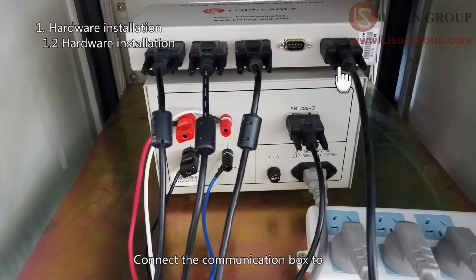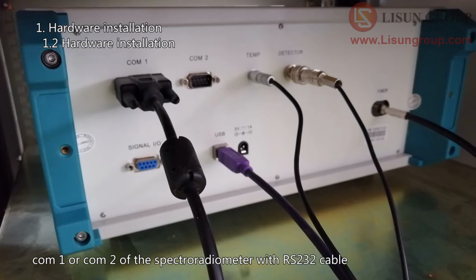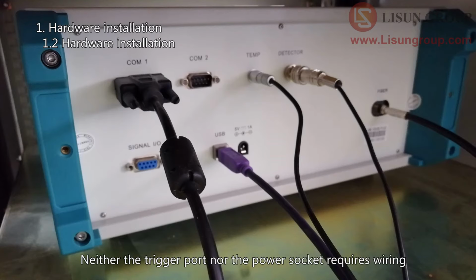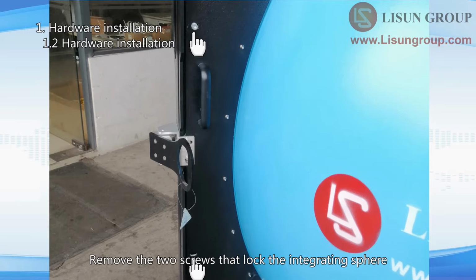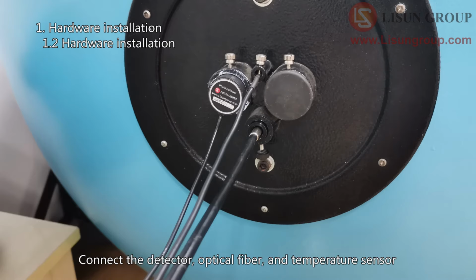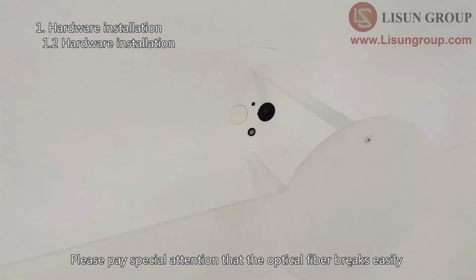Connect the communication box to COM1 or COM2 of the spectroradiometer with RS-232 cable. Neither the trigger port nor the power socket requires wiring. Remove the two screws that lock the integrating sphere. Connect the detector, optical fiber, and temperature sensor to the side of the integrating sphere. Please pay special attention that the optical fiber breaks easily.